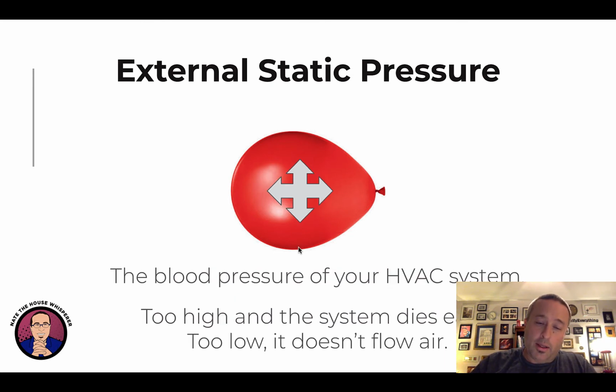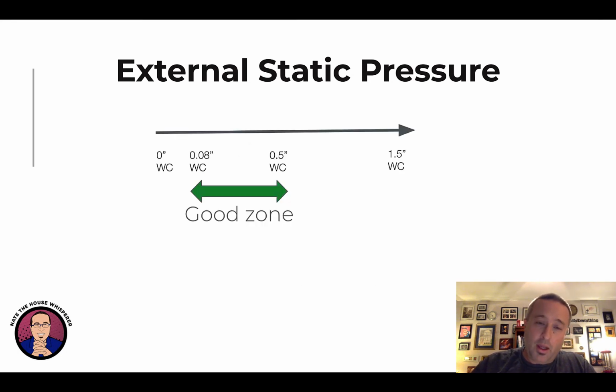So like I mentioned, if static pressure is too high, the system is going to die early. There's a whole bunch of different ways that static pressure can take them out. If it is too low, the system doesn't flow air to the rooms that you want to get it to. So it has to be somewhere in the middle. Here's what the numbers are. So it goes from 0.08 inches of water column to 0.5 inches of water column.